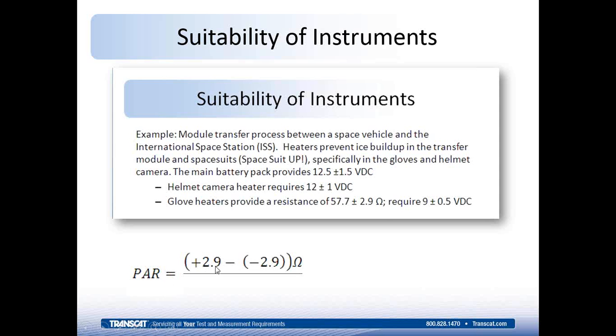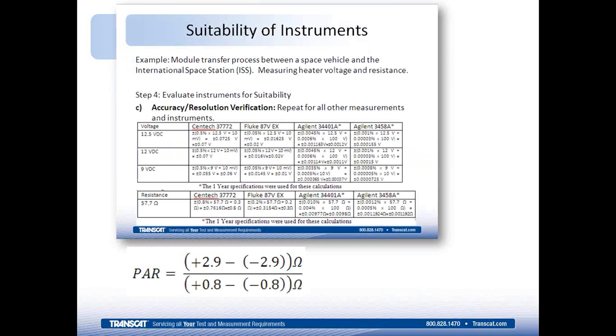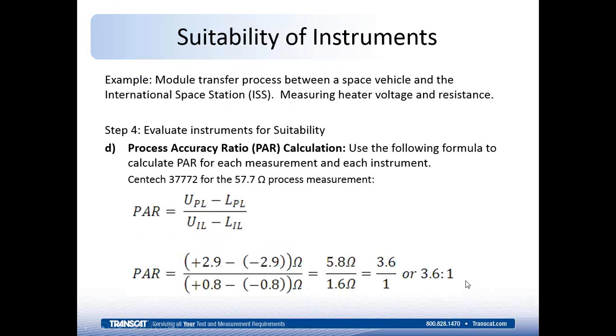So in the process accuracy ratio, we're going to take that 2.9 ohms, and mathematically it comes out to the plus 2.9 minus the negative 2.9 in the numerator for the process. And we're going to divide that by the instrument's accuracy, which for resistance is calculated to be plus or minus 0.8 ohms. So if you look at the table there, for the Centech 37772 on the 57.7 ohm measurement, we took the manufacturer's accuracy statement and converted it to a tolerance in the unit of engineering, which is in ohms, and that's how we got the denominator. All right, so we take the process tolerance in the numerator, the instrument tolerance in the denominator, and we come out with a ratio of 3.6 to 1.